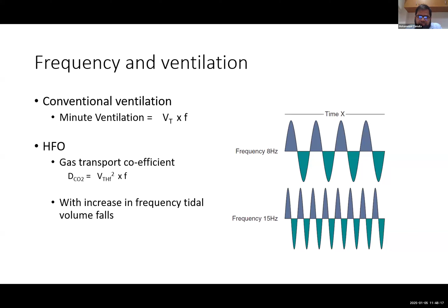As I have discussed initially, inspiratory time represents the portion of the respiratory cycle that the piston spends in the forward motion. As we discussed in the initial slide, the piston moves forward. So that will determine how much time it takes for the piston to reach its position. That is the inspiratory time. Usually we'll keep it at a 1:2 ratio as a norm. So usually we give TI time around 33%, and expiratory time will be around 66%. That is the ideal ratio which we use.